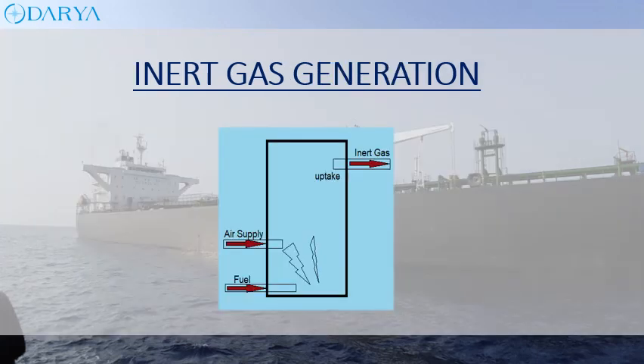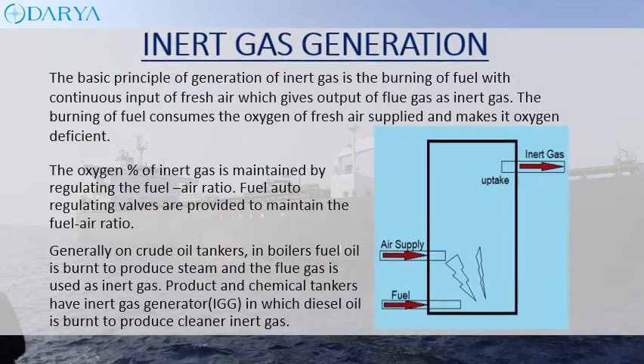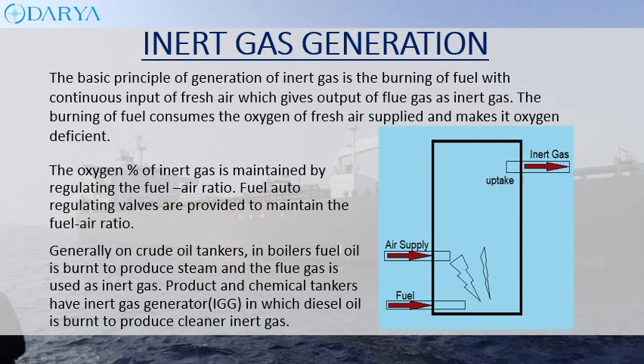The basic principle of generation of inert gas is the burning of fuel with a continuous input of fresh air, which gives output of flue gas as inert gas. The burning of fuel consumes the oxygen of fresh air supplied and makes it oxygen deficient. The oxygen percentage of inert gas is maintained by regulating the fuel-air ratio; fuel auto-regulating valves are provided to maintain the fuel-air ratio.